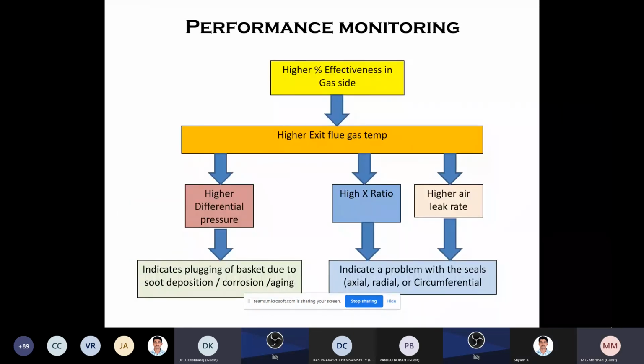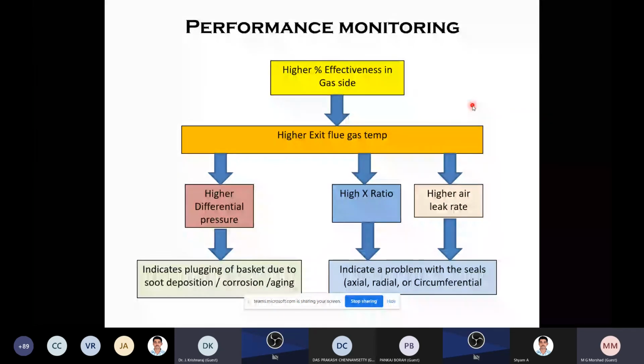Yes, sir. Okay. Now, performance. Then how are you extracting the meaning of such activities? Higher gas side effectiveness, higher exit flue gas temperature, higher differential pressure, higher X ratio, higher air ingress. If you have an idea of all these things, you can very easily give recommendations and arrest the leak or correct the things without any big expenditure. The expenditure of a recommendation is also a very important factor.